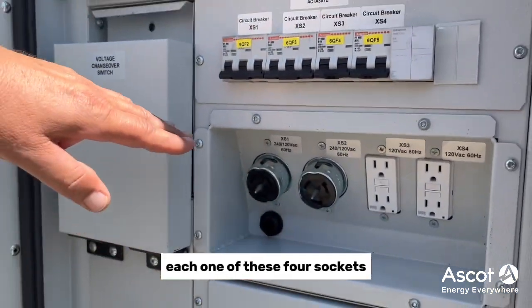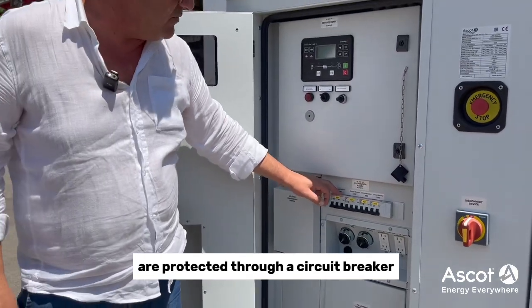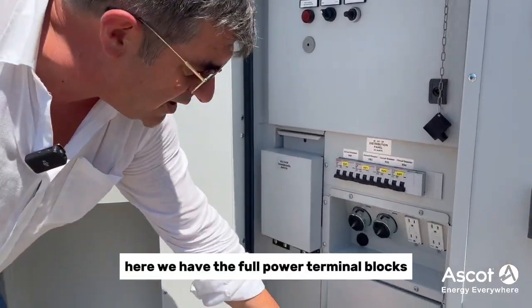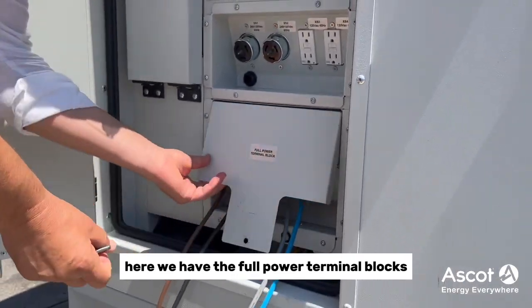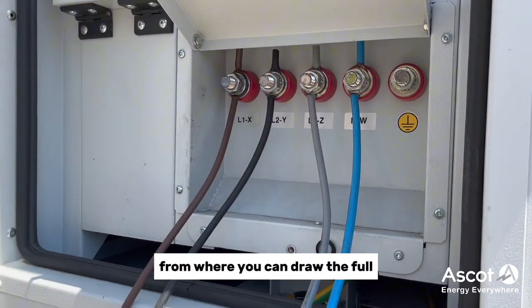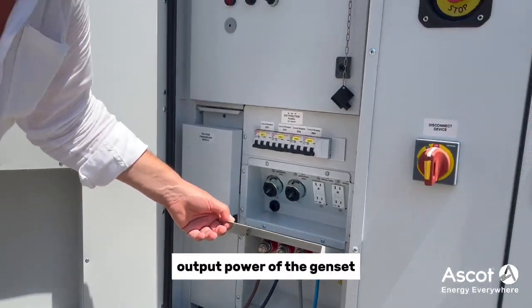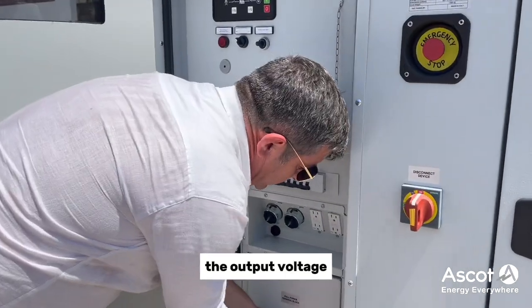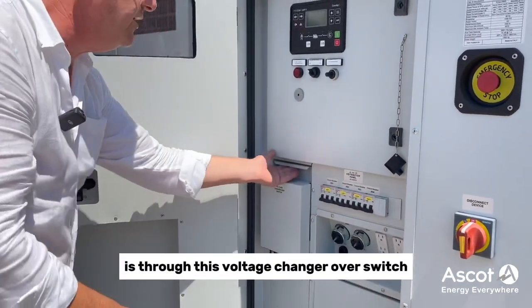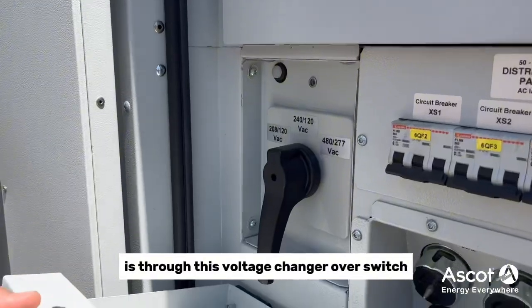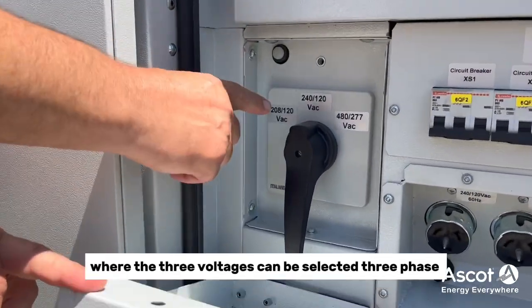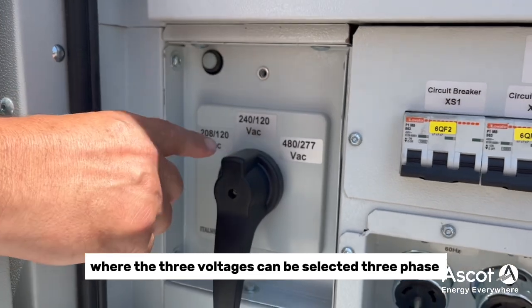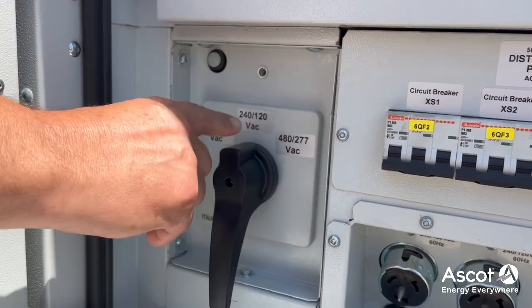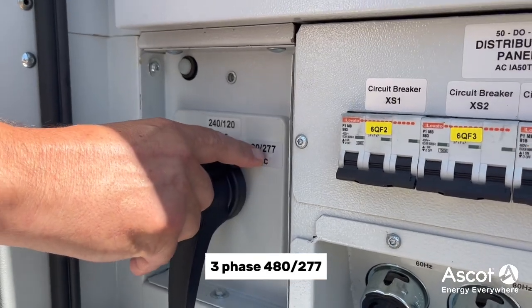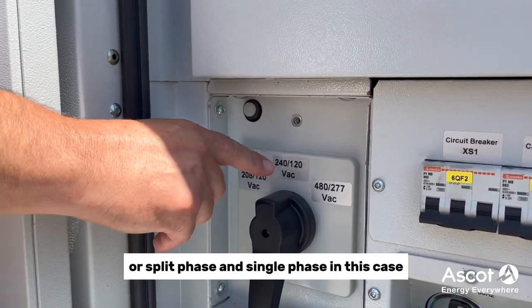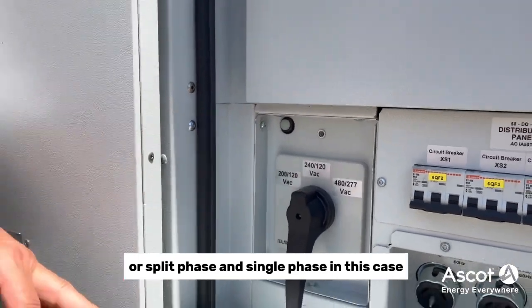Each one of these four sockets is protected through a circuit breaker. Here we have the full power terminal blocks from where you can draw the full output power of the genset. The output voltage is selected through this voltage changeover switch, where the three voltages can be selected: three phase 208 120, three phase 480 277, or split phase and single phase in this case.